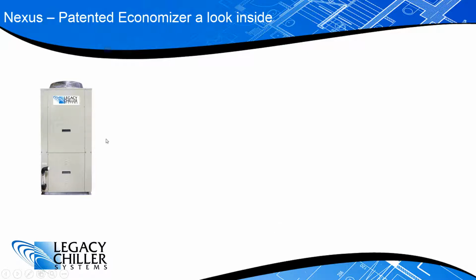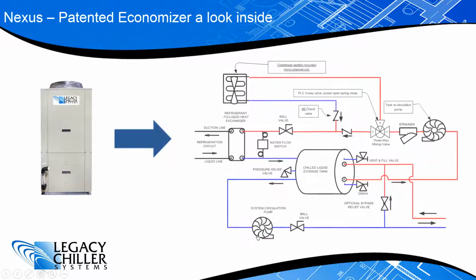All right. So we're going to take a close look at how this is plumbed. So this is, again, one of our PZAT package units, and this is a drawing of the internal plumbing system. I'm just going to go over this real quickly, how this works. So you have two pumps in here. You have a system pump, which is optional. We have many sizes to choose from. We can put anywhere in most models from a third horsepower all the way up to a 10 horsepower if we need to. So this system pump will draw off the tank, go out to the process, come back from the process where it's picked up heat, and back to the tank. So this is called our system pump loop.